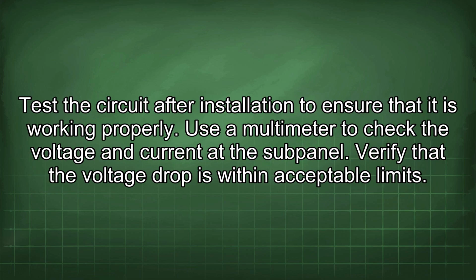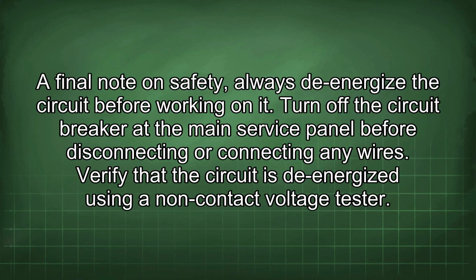Test the circuit after installation to ensure that it is working properly. Use a multimeter to check the voltage and current at the subpanel. Verify that the voltage drop is within acceptable limits. Final note on safety: always de-energize the circuit before working on it. Turn off the circuit breaker at the main service panel before disconnecting or connecting any wires. Verify that the circuit is de-energized using a non-contact voltage tester.